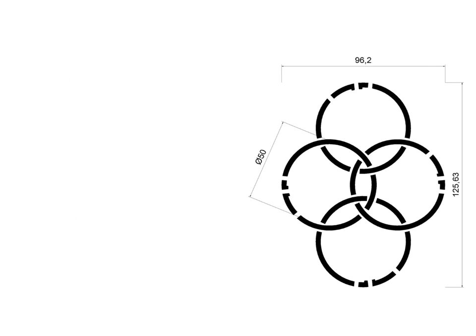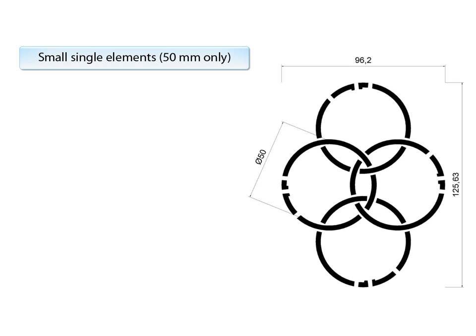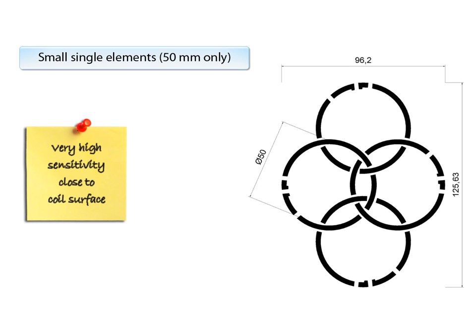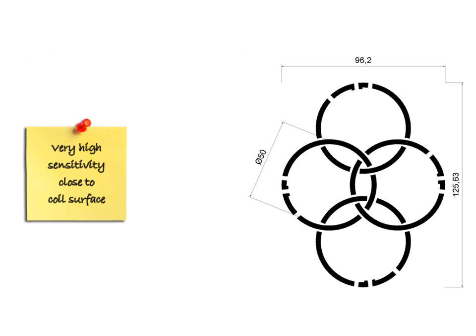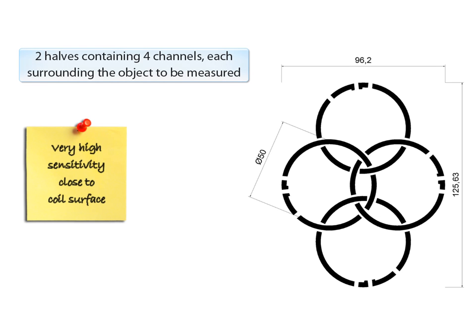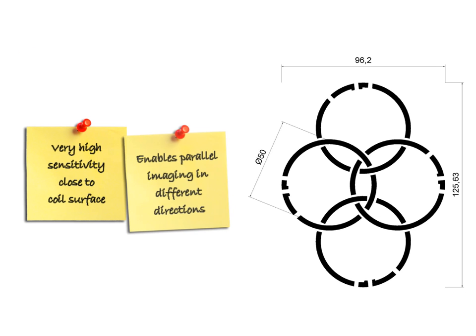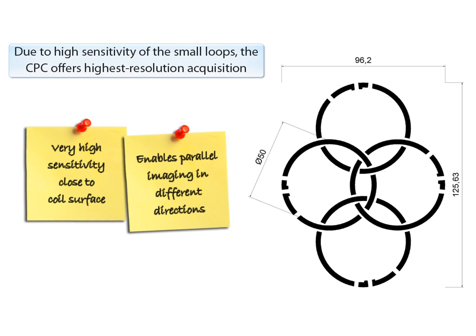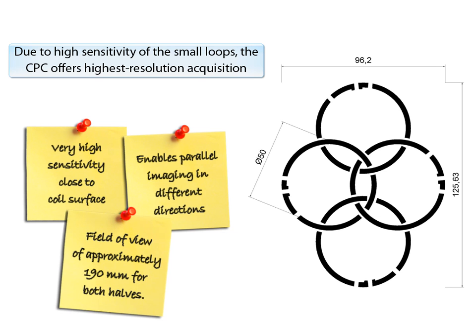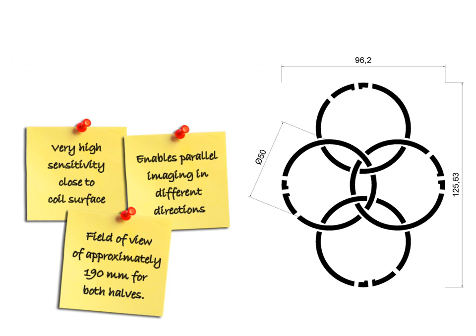Now, let me get a bit further into the physics of the CPC. The specialty of the CPC is its small, single elements with a diameter of only 50 mm internally with very high sensitivity close to the coil surface. Two halves, or shells, containing four channels each, with a total of eight channels, surround the object to be measured. Due to the high sensitivity of the small loops, the CPC offers highest resolution acquisition and offers a field of view, or penetration depth, of approximately 190 mm for both halves. This is still enough for knee images.